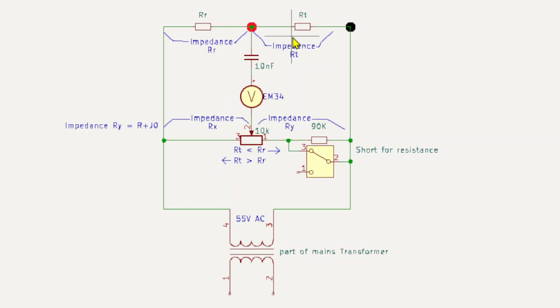Now on the R value, on the low range, the reference impedance or the reference resistor is 2k. So we know to balance the bridge the ratio over here has got to be the same as the ratio there. And so if that's 50-50, then we have to have 50-50 here. So if it's 2k this side, then Rt is 2k and that will balance the bridge and it will null out.